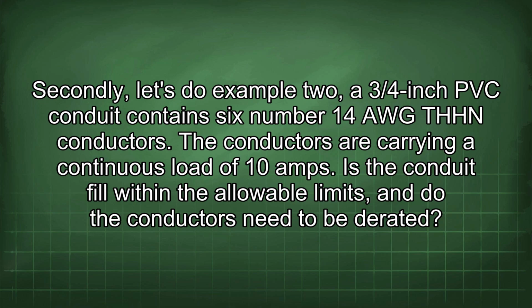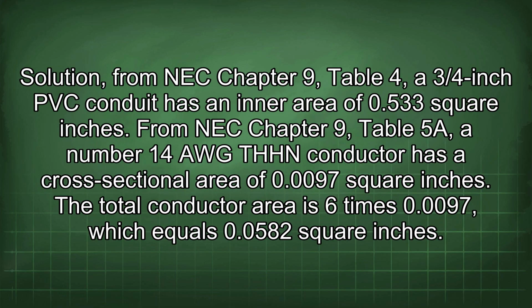A 3/4-inch PVC conduit contains 6 number 14 AWG THHN conductors. The conductors are carrying a continuous load of 10 amps. Is the conduit fill within the allowable limits, and do the conductors need to be derated? Solution from NEC Chapter 9, Table 4. A 3/4-inch PVC conduit has an inner area of 0.533 square inches. From NEC Chapter 9, Table 5a. A number 14 AWG THHN conductor has a cross-sectional area of 0.0097 square inches.